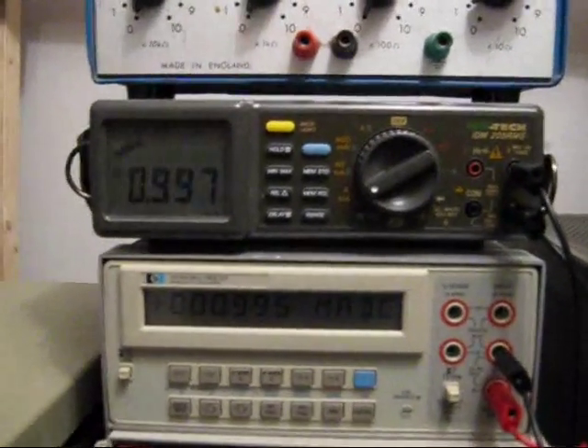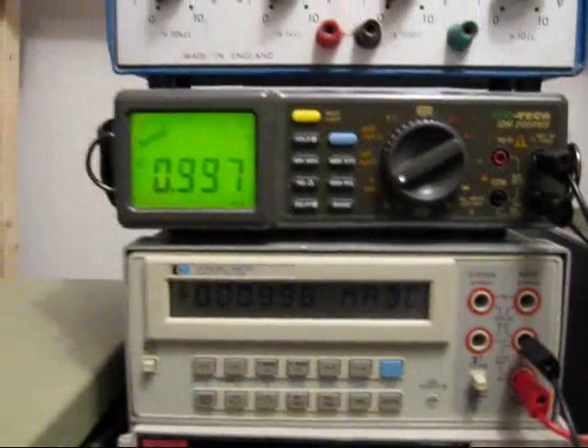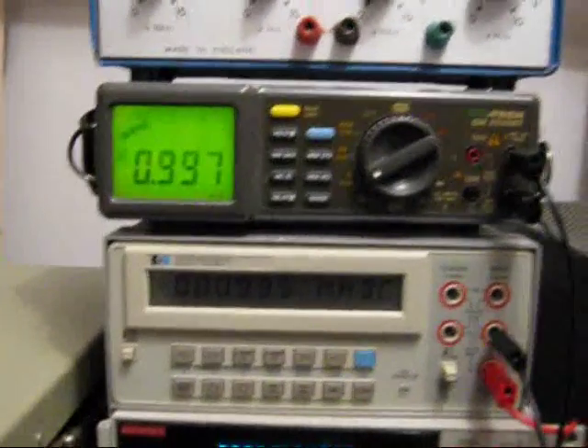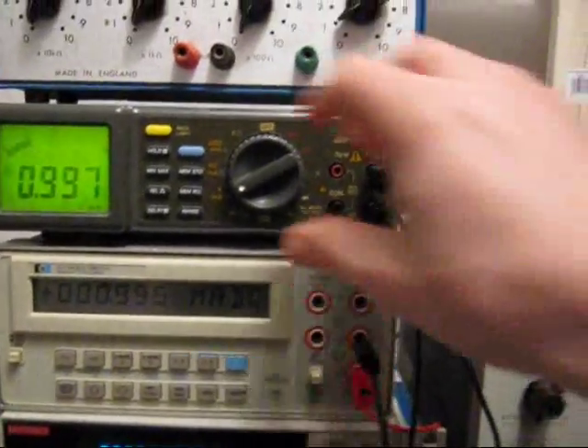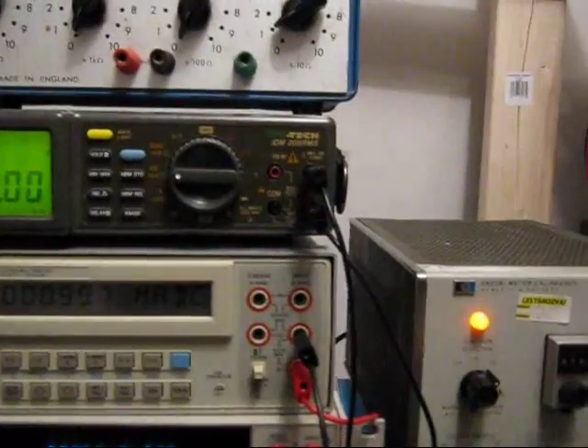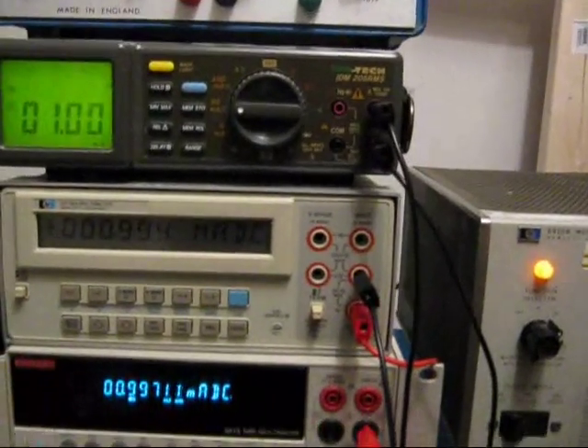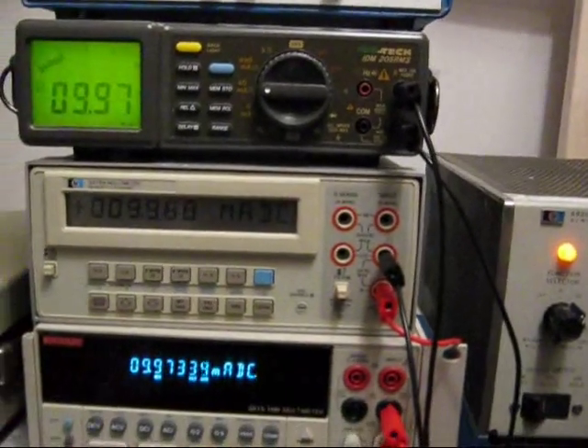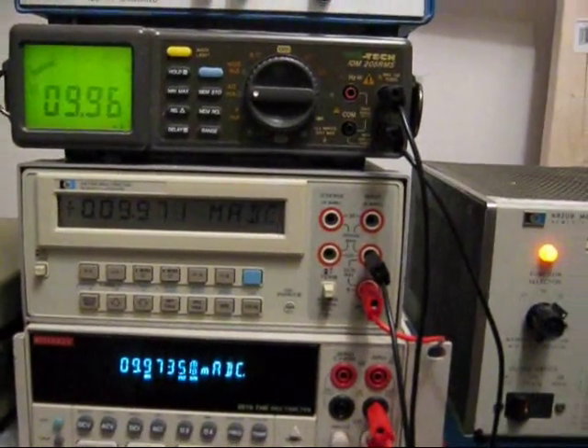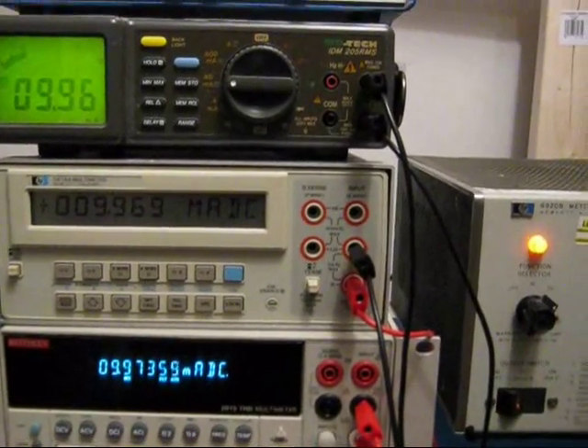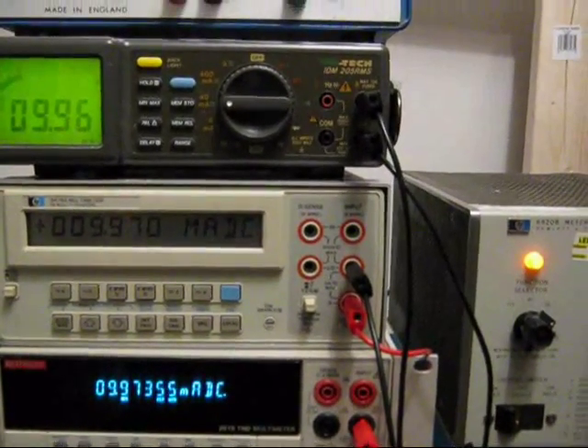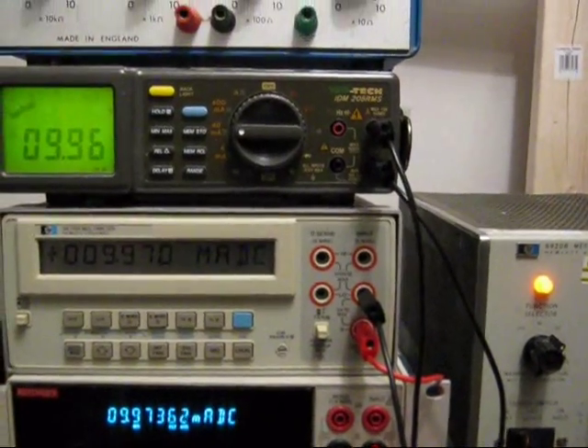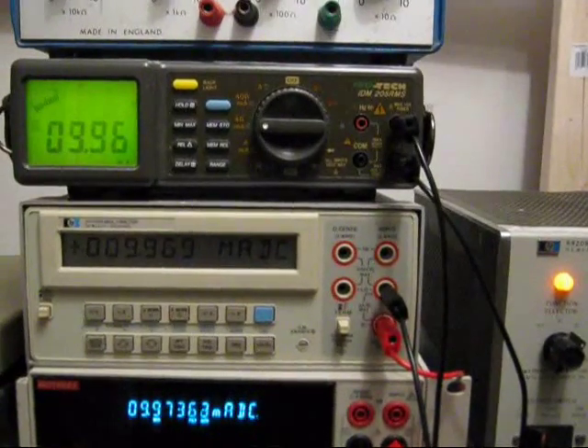The HP is giving us 0.996 of a milliamp. And the Isotech, let's turn its backlight on, is giving us 0.997. We need to switch the range up on the Isotech. And let's go up a range. So now we've got 9.97 on the Keithley, 9.97 on the HP.